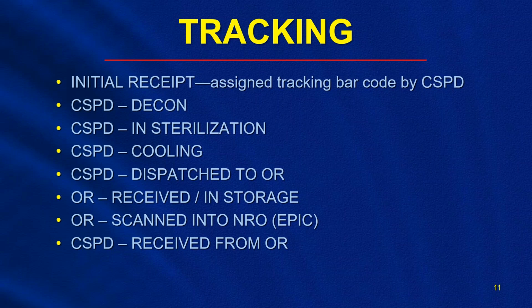So if you look at the slide, on the initial receipt, the tray will be assigned the barcode by Central Sterile Processing, which can tell you also at any point in the system where it is. In Central Sterile, is it in their decon area, their prep and pack area? Is it being sterilized? Is it in the sterilizer? Is it out of the sterilizer and cooling? Has it been dispatched to the OR? Did the OR receive it? And at all these points, the barcode is being scanned. Now, in the OR, we scan it into our nurse's record of operation, directly into Epic. So we know exactly which trays are being used on which patients. And then in Central Sterile, they'll track it when it's received back from the OR for reprocessing after use. So tracking and the ability to track your surgical instruments, as stated, has many, many benefits.